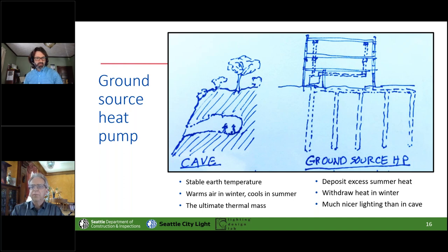There are some technical notes, as Duane points out. It's got a pretty healthy cost, and there are some technical limitations. The well fields are 300 to 400 feet deep and spaced more or less on 20 by 20 foot centers. And you get a ton and a half to 2 tons. These are hand wave numbers, but they're good for guessing per well.